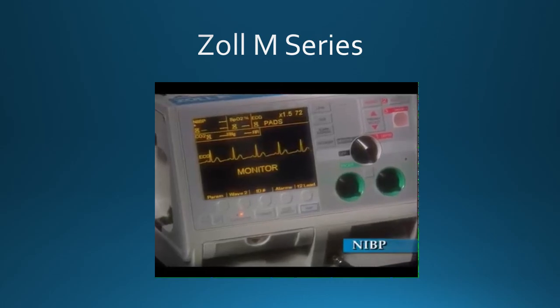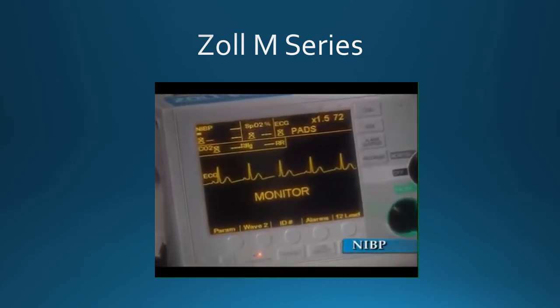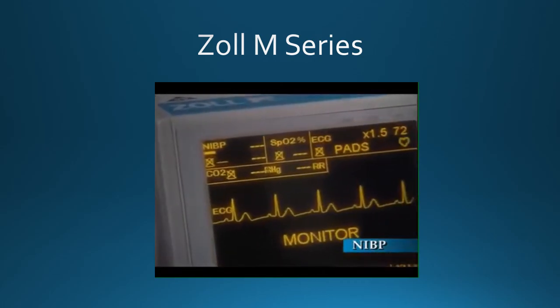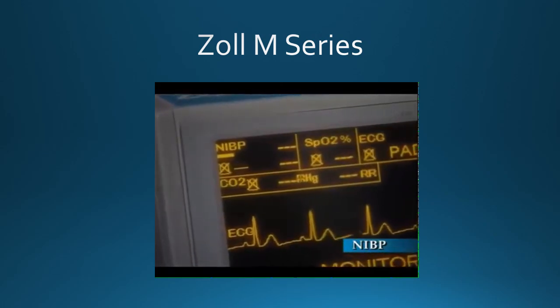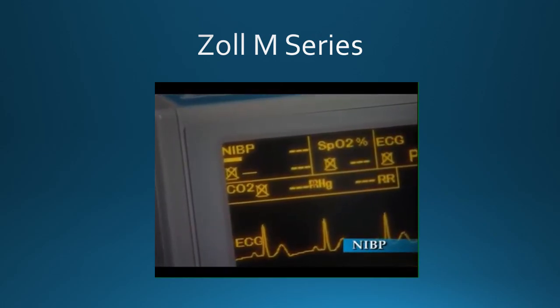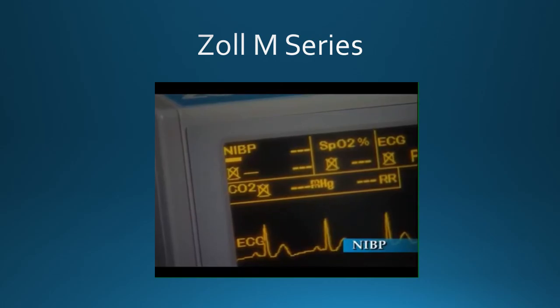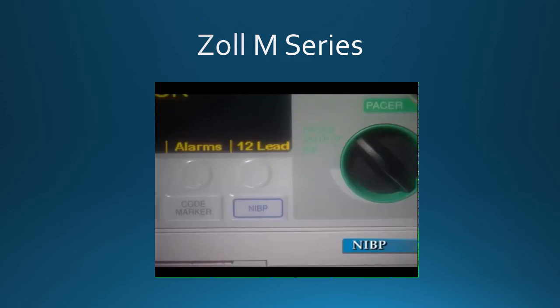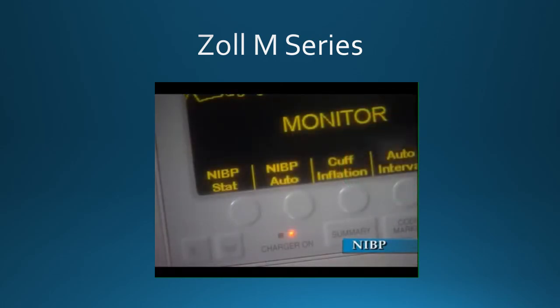The cuff inflation bar reflects the status of the cuff inflation pressure. This cycle takes approximately 30 seconds. The M-Series will not start a new measurement unless 30 seconds have elapsed since the end of the previous completed measurement cycle. To take stat measurements, press the NIBP button and hold it for 2 seconds. Or press the NIBP Stat soft key.